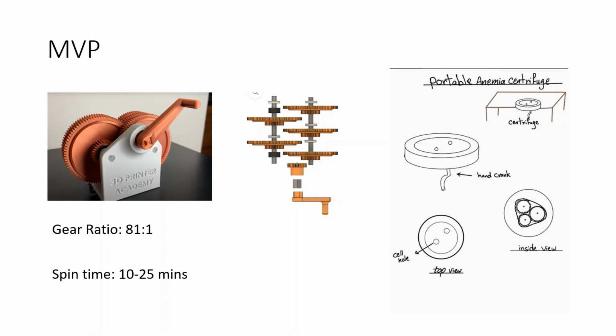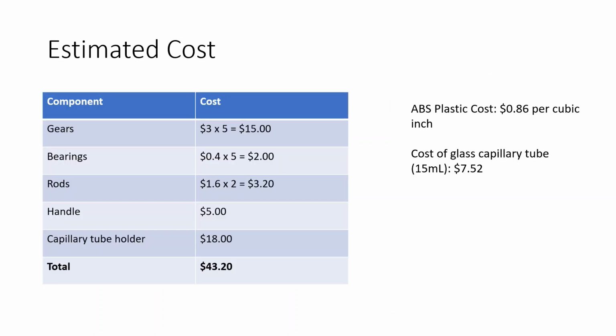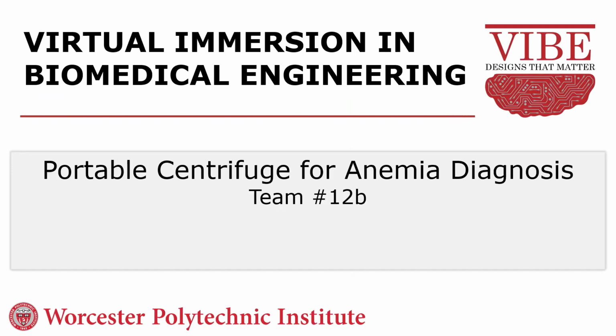The device uses 5 gears with a gear ratio of 81 to 1, which will cause the final gear to rotate at 4,000 revs per minute, which is suitable for separating blood and is similar to many current electric centrifuges. The device is made out of ABS plastic, which is a thermoplastic known for being durable, chemical and heat resistant, and lightweight. ABS plastic costs 86 cents per cubic inch, and it can be used in most 3D printers, making it very accessible. By estimating the volume of each component of the centrifuge, we calculated the total cost to be around $43.20. Thanks for watching.